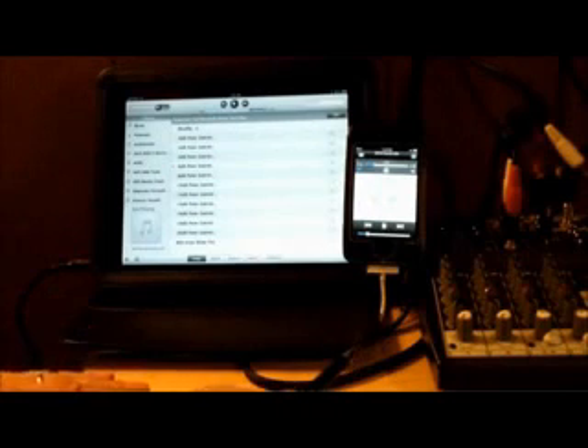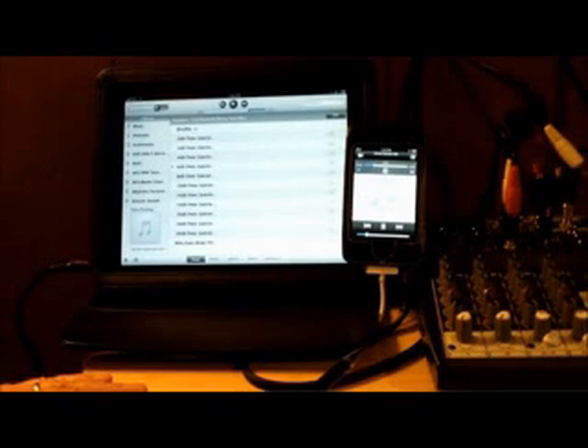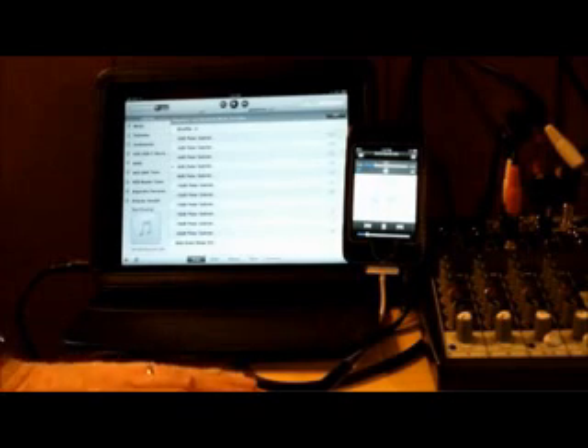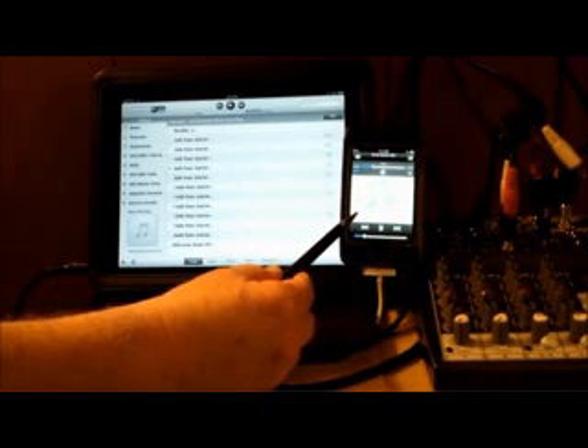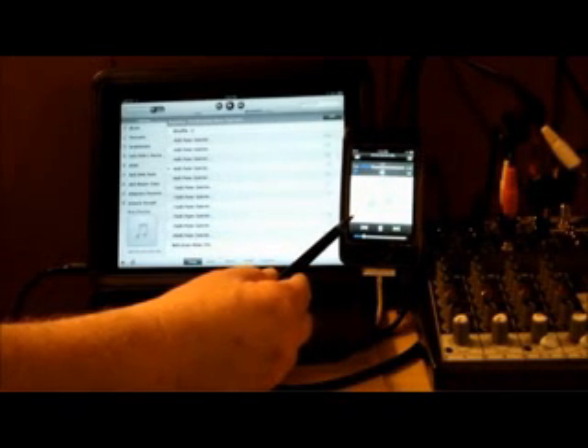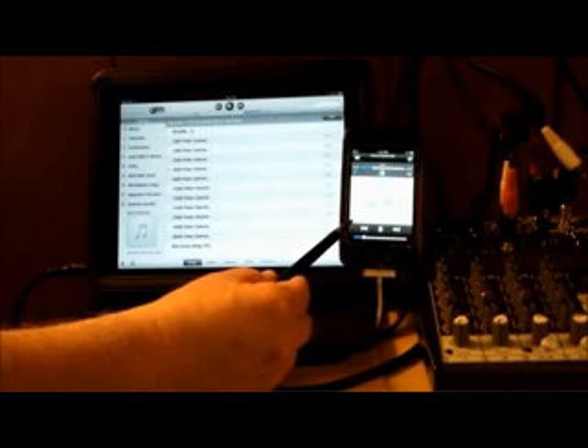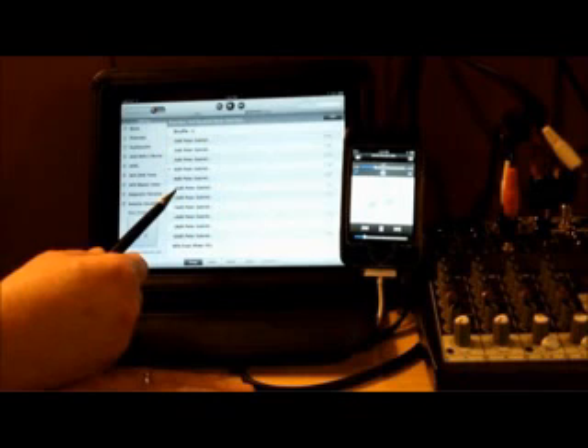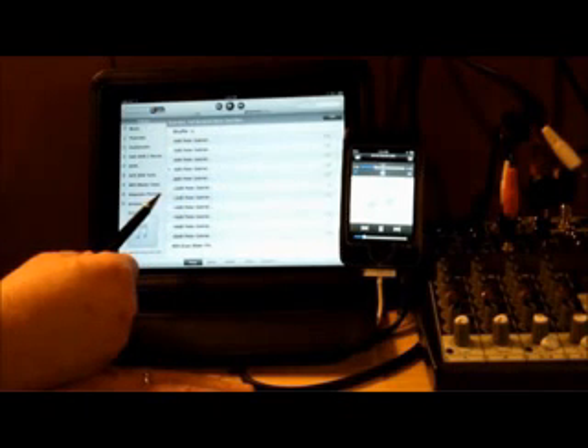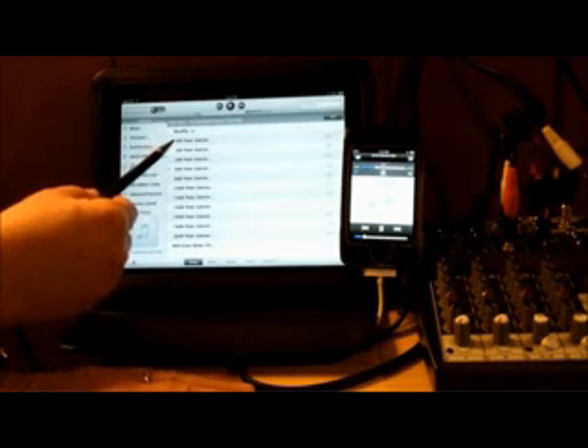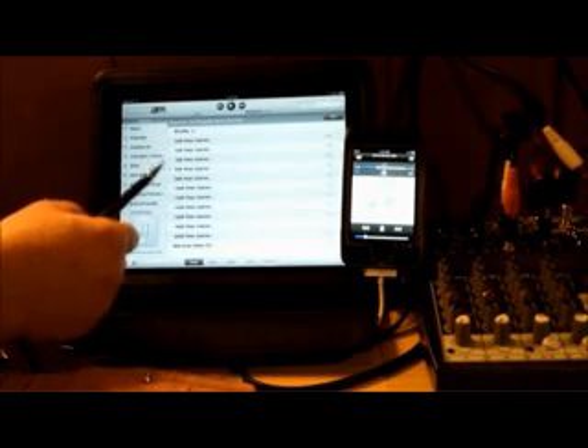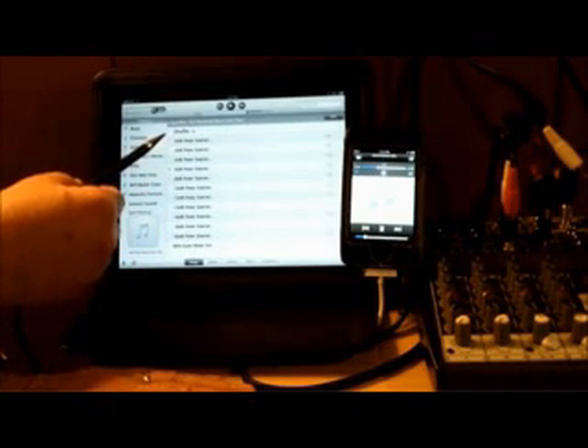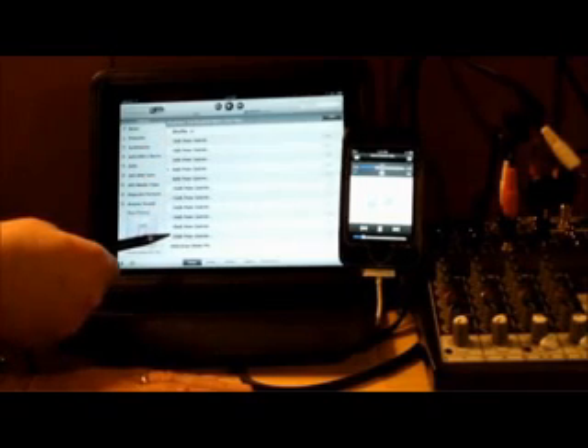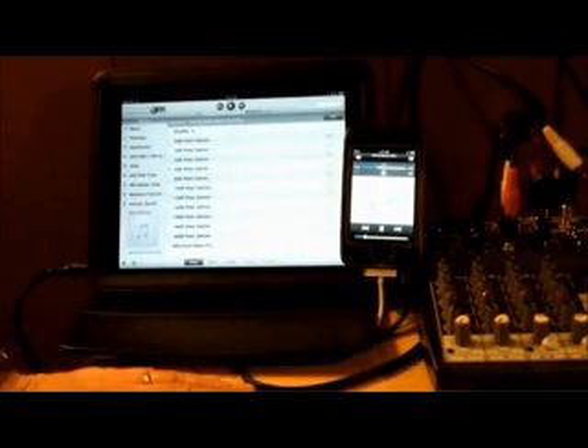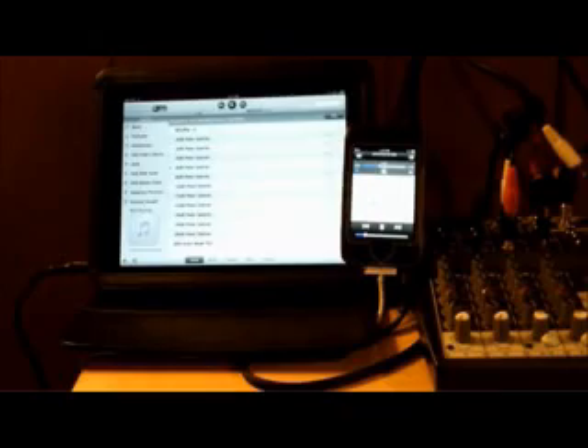Here we see the electrical setup that's going to be used to create our test signal and detector for the Stapedius measurement. Detection of the volume change will come from a tone that's being played by this device, which is at about 230 Hertz, and as the volume level changes within the trapped volume, we'll be able to make that determination. This will play the excitation signal designed to stimulate the Stapedius reflex. It has about a 1-minute selection of a Peter Gabriel song that's been recorded at various levels. We start with a maximum level we'll call 0 dB, and then in 2 dB steps all the way on down to minus 20 dB. These two signals are combined in this small mixer, which in turn drives the receiver under test.